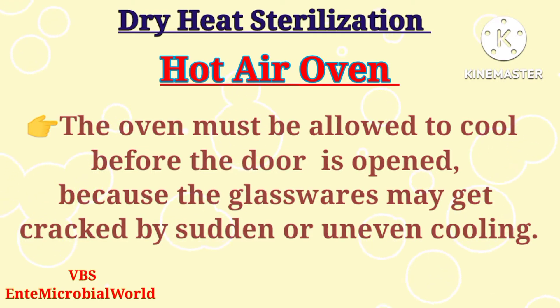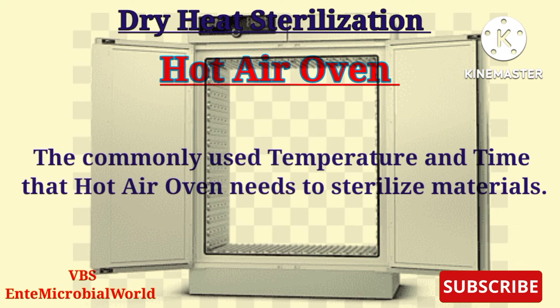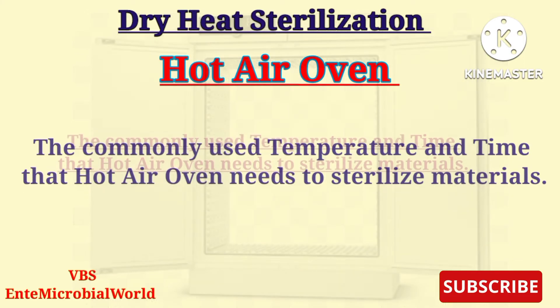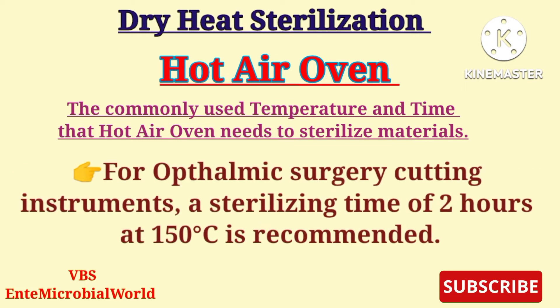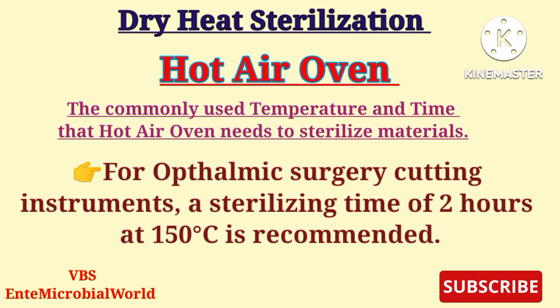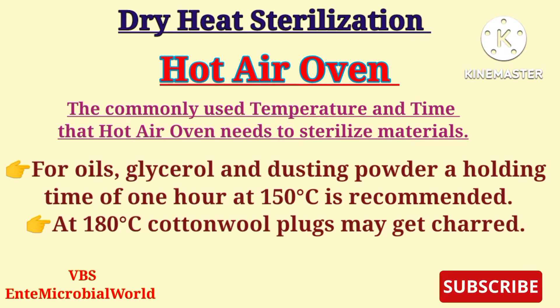Commonly used temperatures and times for the hot air oven: for laboratory glassware, a holding time of two hours at 160 degrees Celsius is sufficient. For ophthalmic surgery cutting instruments, a sterilizing time of two hours at 150 degrees Celsius is recommended. For oils, glycerol, and dusting powder, one hour at 150 degrees Celsius is recommended. Note: at 180 degrees Celsius, cotton wool plugs may get charred.